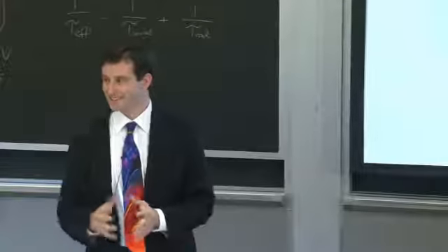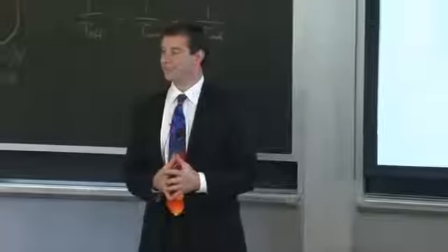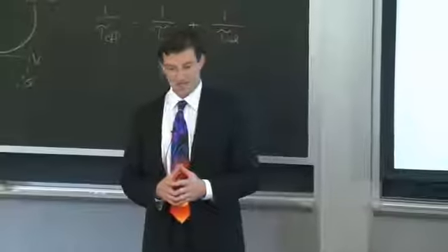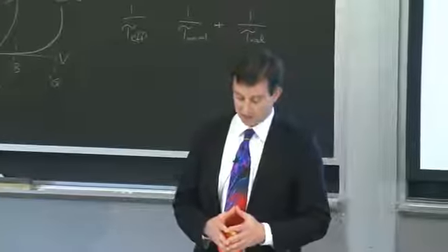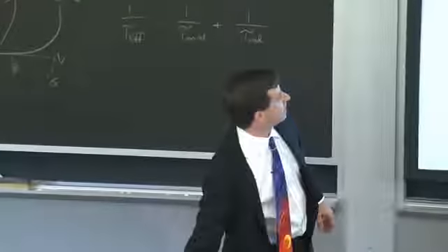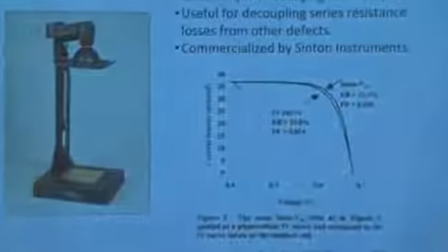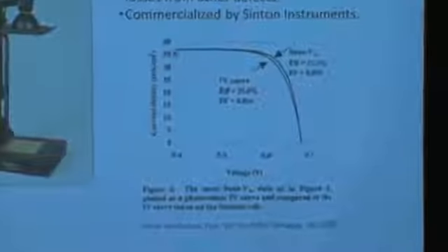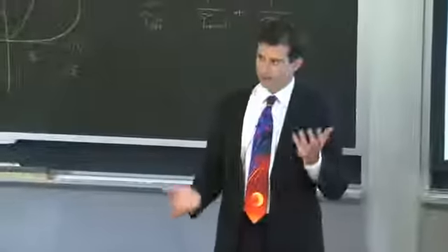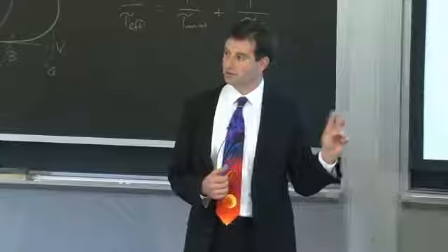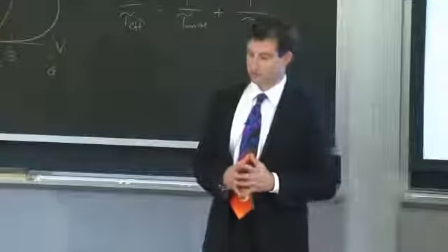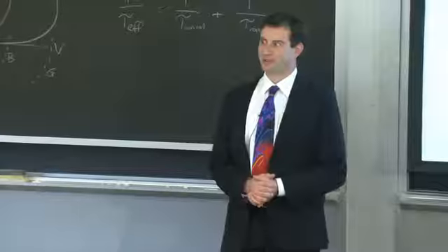The light source in the Suns-Voc, that's not a solar simulator in any way, is it? No. Is that important? Yeah, it is important. It would be a different, in essence, a different current response, right, if you didn't have the same exact solar spectrum. Now, that's a very important point. If you're venturing outside of, say, silicon-based devices, and you're more sensitive to the infrared or the UV, you really want to make sure that you measure the intensity as a function of wavelength output of that bulb. Otherwise, you might be higher or lower during the Suns-Voc measurement.